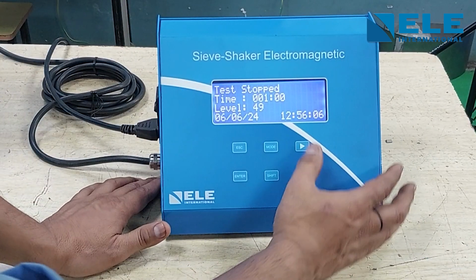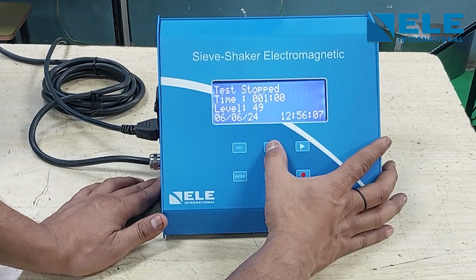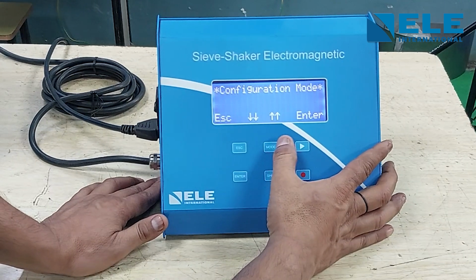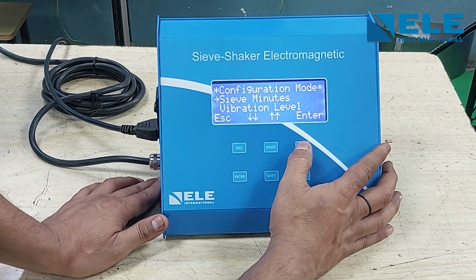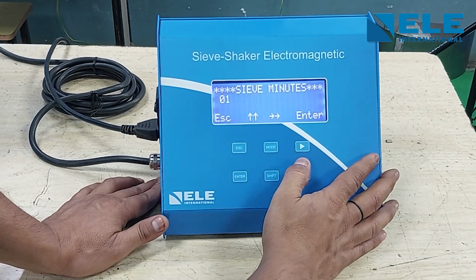Apply power to the sieve shaker by switching the main switch on the control module. As we switch on the power supply, the first screen visible to us is the same screen that is visible when we stop the process using the stop key. As we click on the mode button, the configuration mode window will open.